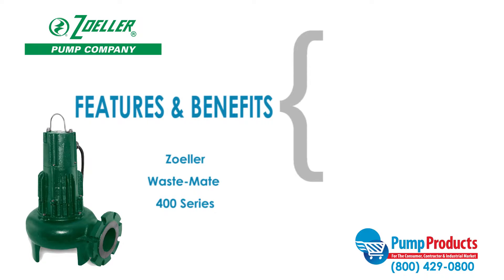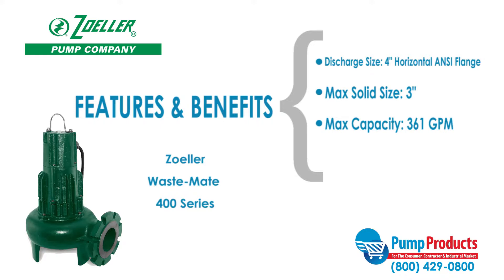Some features and benefits of the Zoeller Waste-Mate 400 series include a discharge size of 4 inches horizontal ANSI flange, a max solid handling ability of 3 inches, maximum capacities of 361 gallons per minute, and a maximum head of 38 feet.